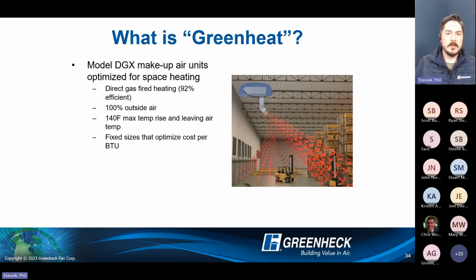So now we're superheating the air, effectively bringing in outside air for fresh ventilation, superheating it to 140 degrees, and the space condition is what's driving that enable and disable. Once we satisfy the space condition, the whole unit disables. So direct gas fired heating, 92% efficient, 100% outside air, and 140 degree max temp rise or leaving air temperature, to get the space temperature up to 65 or 70 degrees as fast as possible, and then cycle off. Fixed sizes that optimize the cost per BTU.